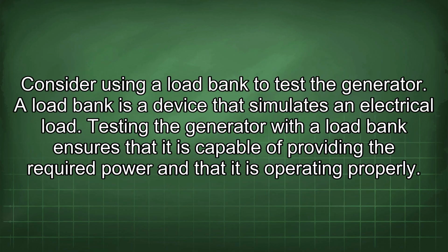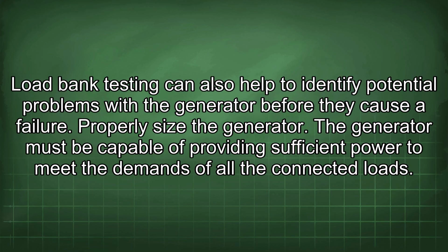Consider using a load bank to test the generator. A load bank is a device that simulates an electrical load. Testing the generator with a load bank ensures that it is capable of providing the required power and that it is operating properly. Load bank testing can also help to identify potential problems with the generator before they cause a failure. Properly size the generator.